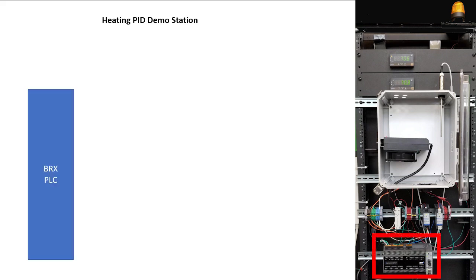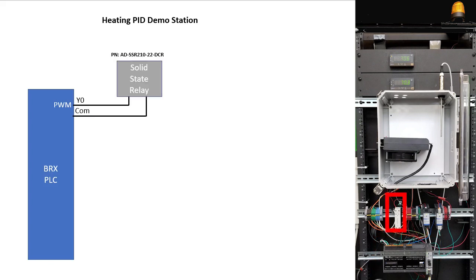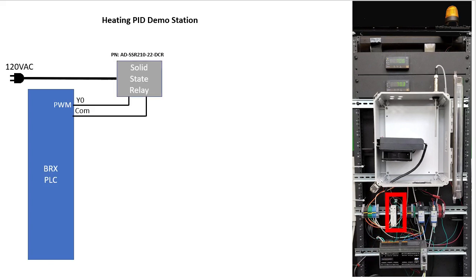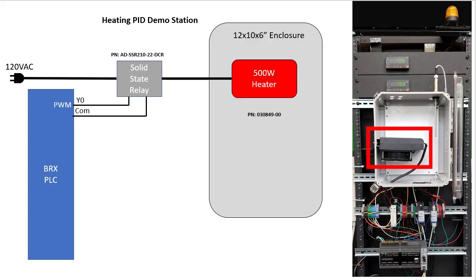We'll do that by configuring a BRX PLC output to be a pulse width modulated or PWM signal. That will control this solid state relay which will toggle the 120 volt AC power into the 500 watt resistive fan heater.